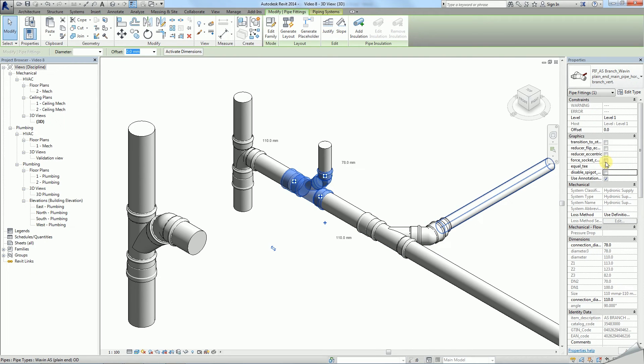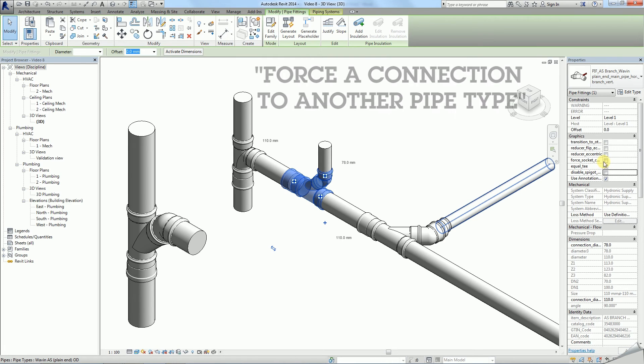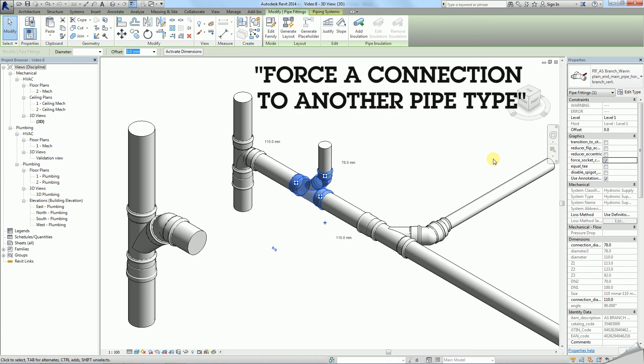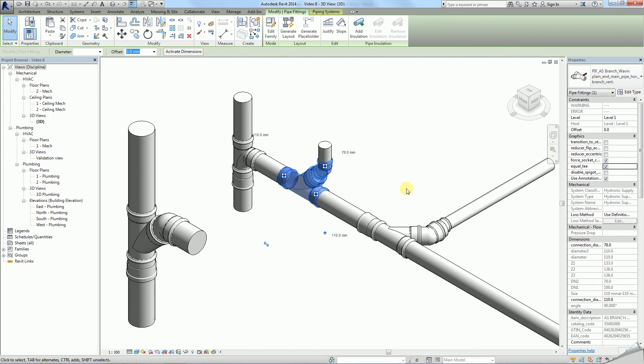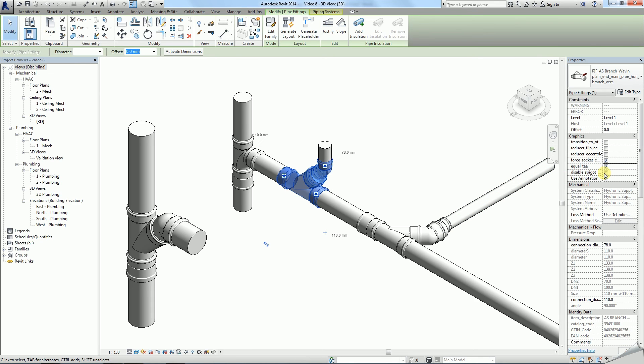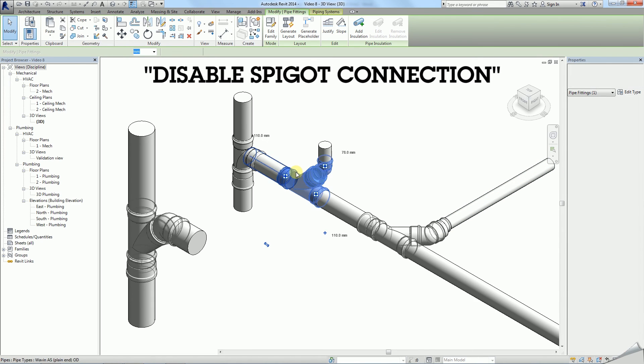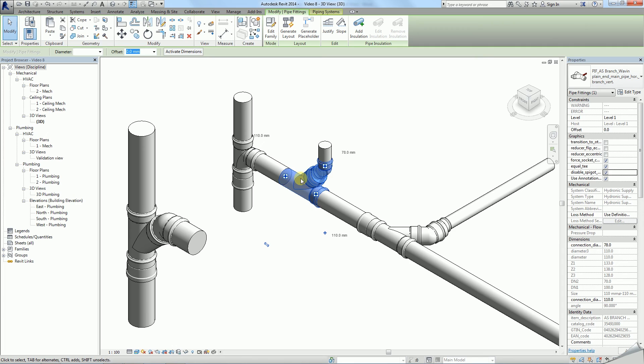Furthermore, a number of useful options are available in the properties of a T. Within eccentricity options you are able to force a connection to another pipe type, in case you combine plain ended pipes to socketed ones. You can also force use of equal T if this better suits the situation. Finally, the disable spigot connection helps if you connect family directly to another fitting.